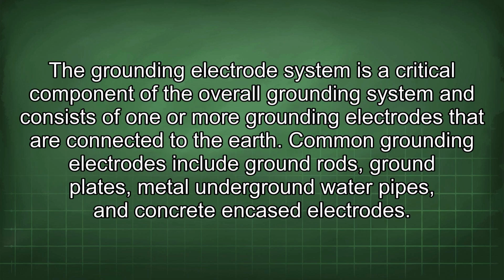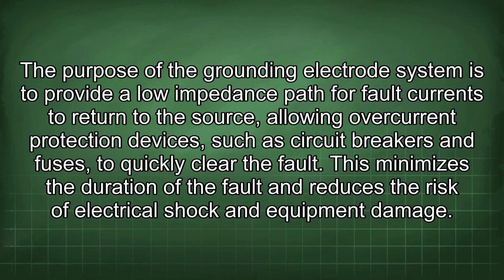The grounding electrode system is a critical component of the overall grounding system and consists of one or more grounding electrodes that are connected to the earth. Common grounding electrodes include ground rods, ground plates, metal underground water pipes, and concrete encased electrodes. The purpose of the grounding electrode system is to provide a low impedance path for fault currents to return to the source, allowing overcurrent protection devices such as circuit breakers and fuses to quickly clear the fault. This minimizes the duration of the fault and reduces the risk of electrical shock and equipment damage.